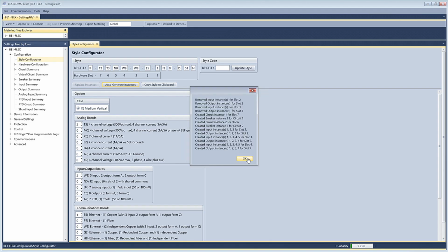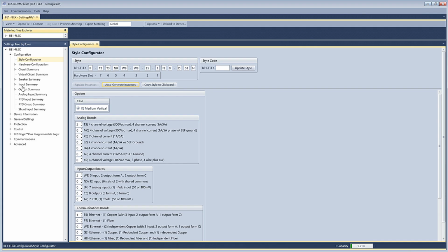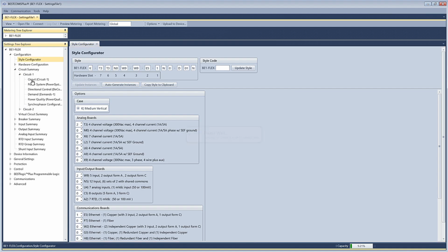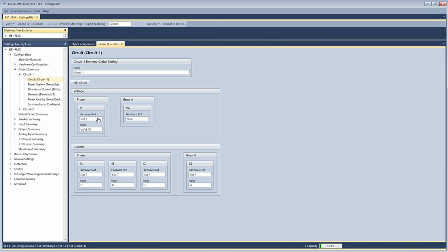Another way to think of this configuration is going to be the analog to digital conversion. We're bringing in analog devices, and we're ultimately processing them with a microprocessor, which is a digital component. So for the circuit piece, it had taken slot 7 hardware, looking at voltage ABC, and applied it to circuit 1's voltage phase.